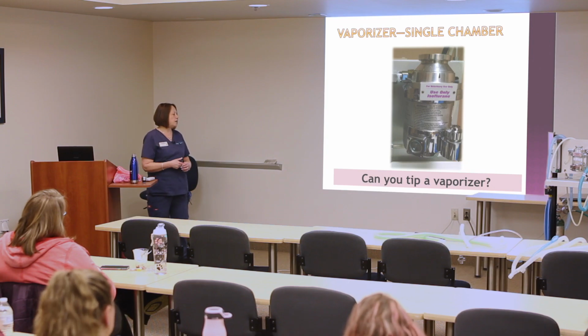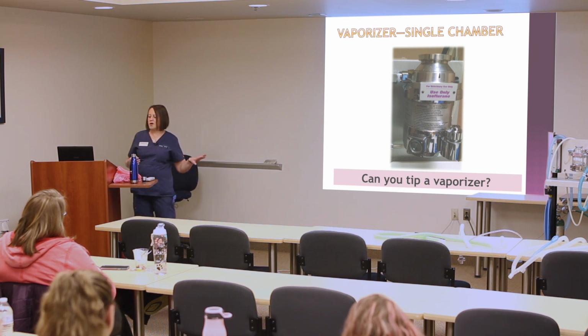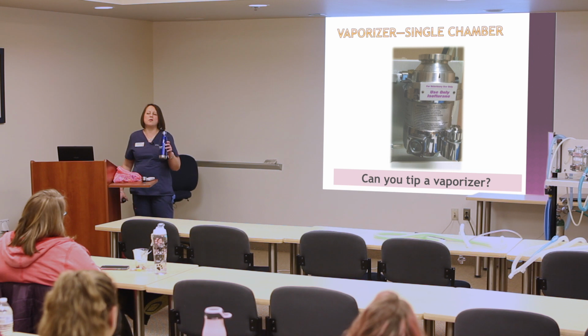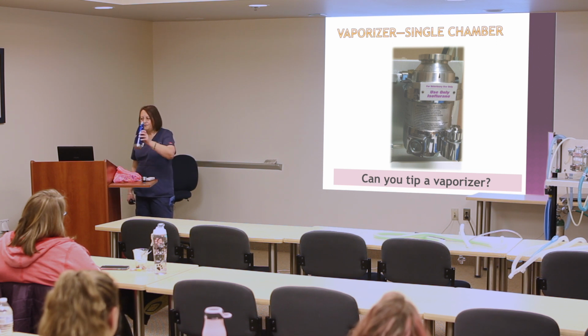And does anybody know what degrees you cannot tip a vaporizer? So I put here, all vaporizers must remain level to function properly. Does anybody know how far you can tip a vaporizer before you have to have it serviced? It's real nerd information. 45 degrees. So if for some reason somebody tripped and fell over that machine and it landed on the ground or it got tipped more than 45 degrees, whatever you have dialed on the vaporizer won't all of a sudden be accurate. So you might have 2% dialed, they could be delivering 5% or 0%. And so if that ever happens, let me know, because the vaporizer has to get drained and dried out. There's a wick in there, or it would have to go out for service.